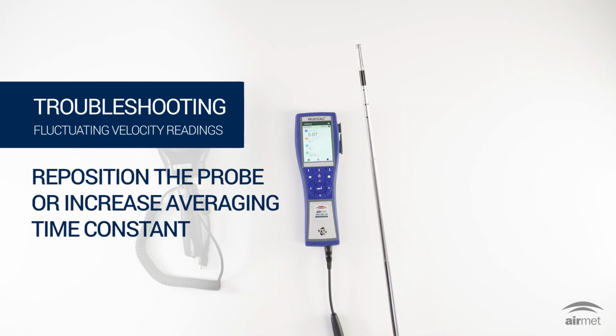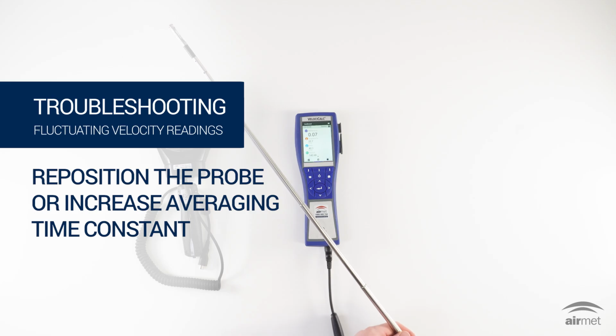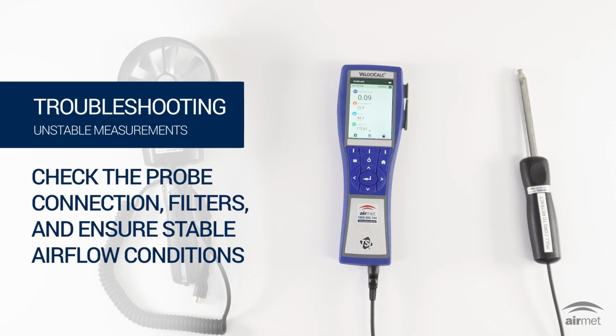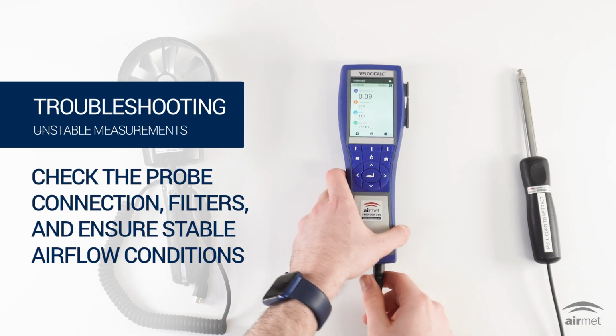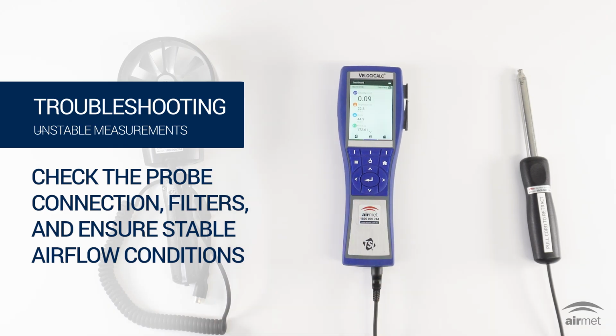Fluctuating velocity readings. To resolve fluctuating velocity readings, reposition the probe or increase the averaging time constant. Unstable measurements. For unstable measurements, check the probe connection, filters, or ensure stable airflow conditions.